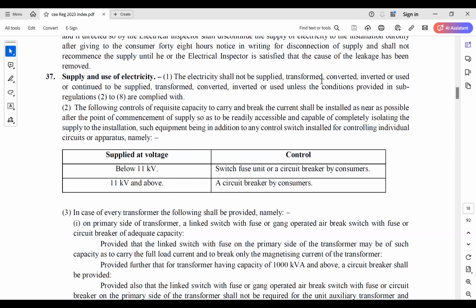Sir, in my factory, for example, the actual connected load is 300 kVA in one of the factories. Now, there is an RMU. At the outgoing, there is a circuit breaker, VCB. The transformer is about 100 meters away. There is one more circuit breaker near the transformer. Now, this part is okay.